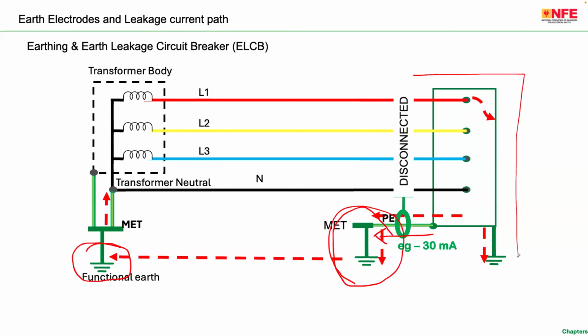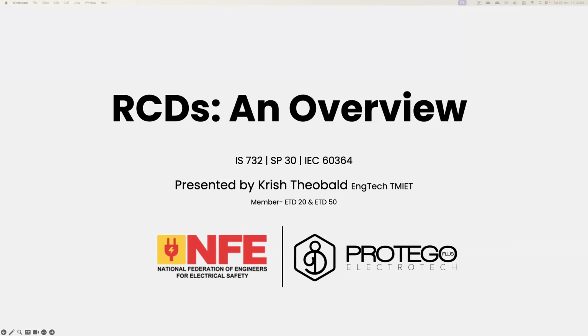As a result, the body of the equipment will be energized, and if somebody touches it at that particular time, people get shocked. So in an ELCB, I'm talking about current operated ELCB. Krish will explain about voltage operated ELCB. In a current operated ELCB, the leakage current through the PE conductor is measured. That means there should be a PE conductor and a proper earth electrode. So this is a very small introduction about the ELCB. Now I would like to stop the presentation and invite today's speakers to take over. First, Krish will start with his presentation, followed by Mr. Gerard. Over to you, Krish.